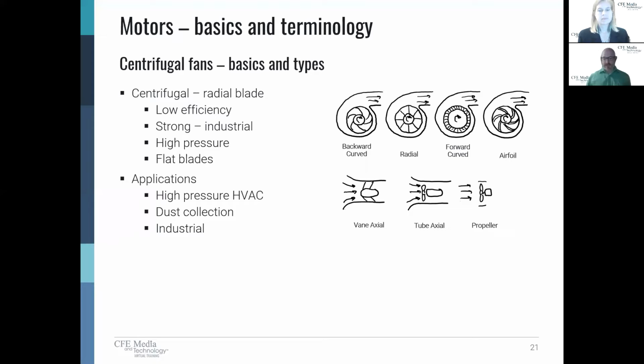Now, a centrifugal fan requires a casing. If you were to just set this fan out in the middle of nowhere, you'd produce some air movement, but it wouldn't be very useful, unlike a propeller fan, which you can just set down and it's going to do something. It's going to move air. So the casing is very important. The shape of the casing is also going to affect the efficiency. Now, there's a couple different types here. We're going to touch on each one.